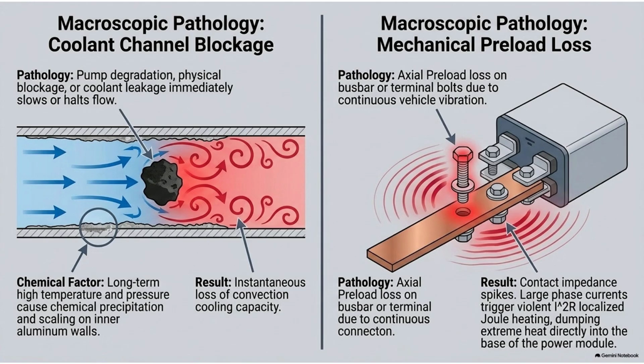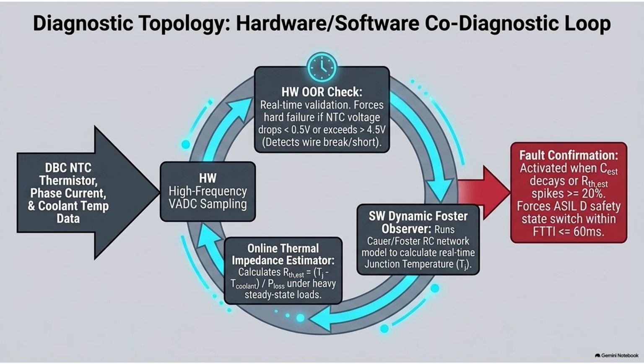Right. It's a chemical degradation process. Over time, the chemical composition of the liquid coolant interacts with the hot aluminum walls under high pressure. Even with the special EV coolants. Even with specialized automotive coolants, the extreme heat can cause minerals and chemical compounds to physically precipitate out of the liquid. They separate from the fluid and bake onto the inside walls of the cooling channels.